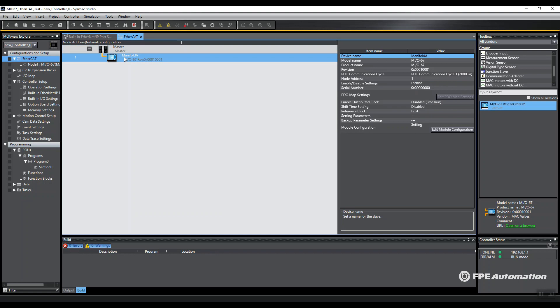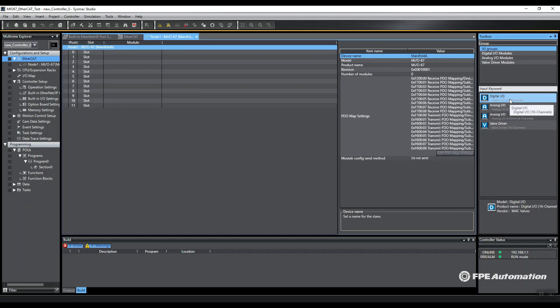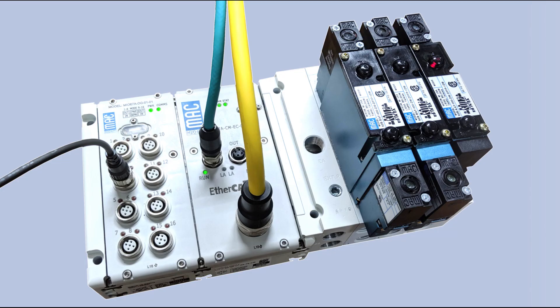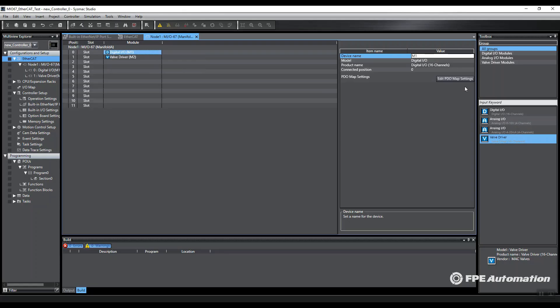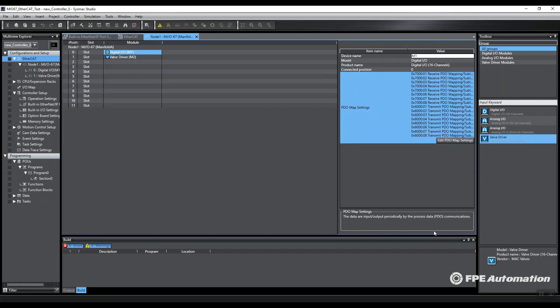Now my manifold here has an input block attached to it, so I want to make sure it's properly configured. I go to edit module configuration, and this is my dictionary of items I can add. I first want to go from left to right, make sure I'm offline first, add my digital I/O block followed by my valve driver, and because my I/O block can be inputs or outputs, I want to enable both. Hit apply and okay.